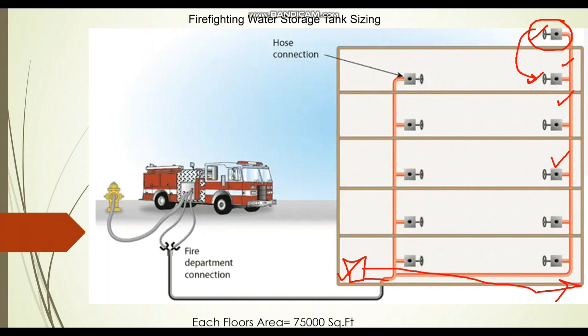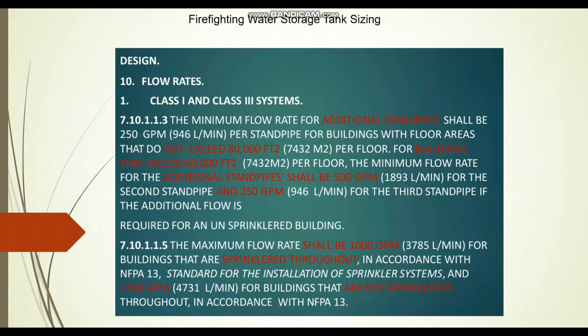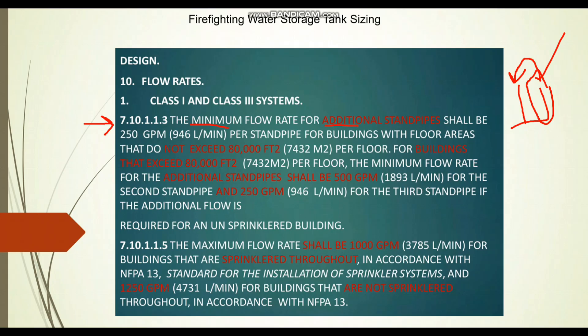Coming to the next riser, we have two conditions to follow. We need to check the floor area. In this project each floor area is 75,000 square feet. As per NFPA 14, for the additional standpipe, we consider 250 GPM if the floor area does not exceed 80,000 square feet. If any floor area exceeds 80,000 square feet, then we must consider 500 GPM for the additional standpipe.